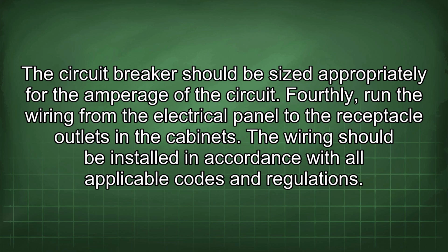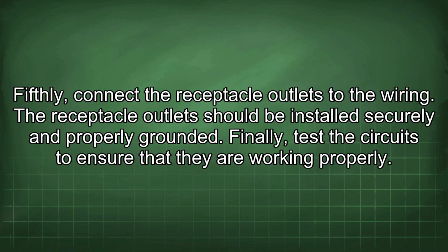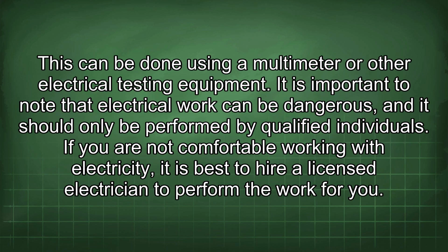Fourthly, run the wiring from the electrical panel to the receptacle outlets in the cabinets. The wiring should be installed in accordance with all applicable codes and regulations. Fifthly, connect the receptacle outlets to the wiring. The receptacle outlets should be installed securely and properly grounded. Finally, test the circuits to ensure that they are working properly. This can be done using a multimeter or other electrical testing equipment. It is important to note that electrical work can be dangerous, and it should only be performed by qualified individuals. If you are not comfortable working with electricity, it is best to hire a licensed electrician to perform the work for you.